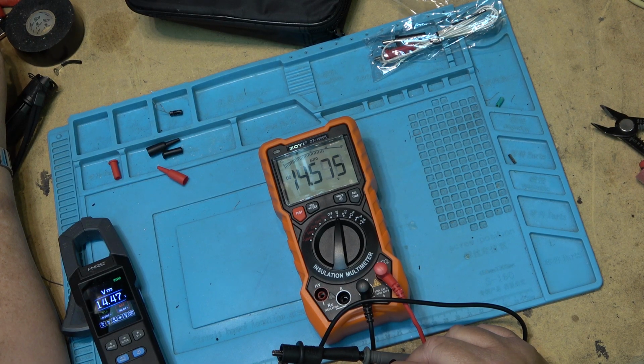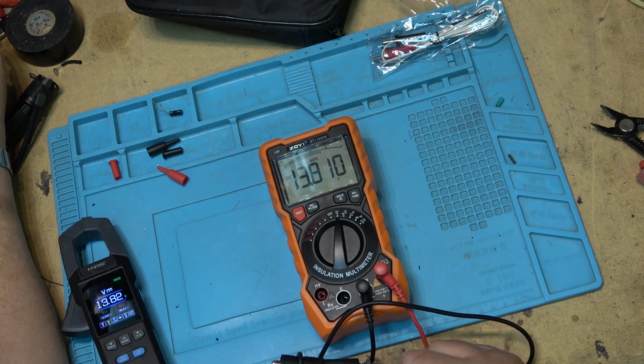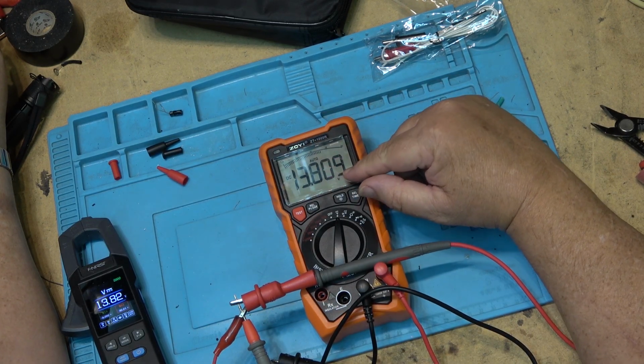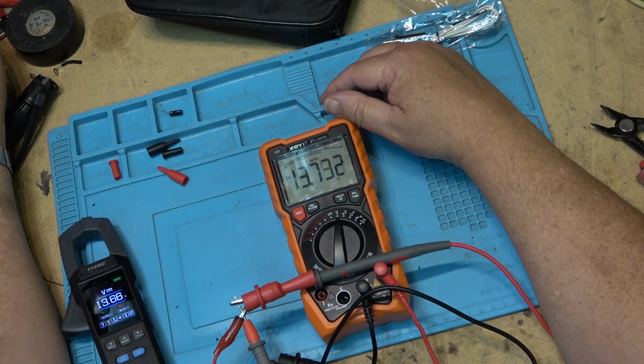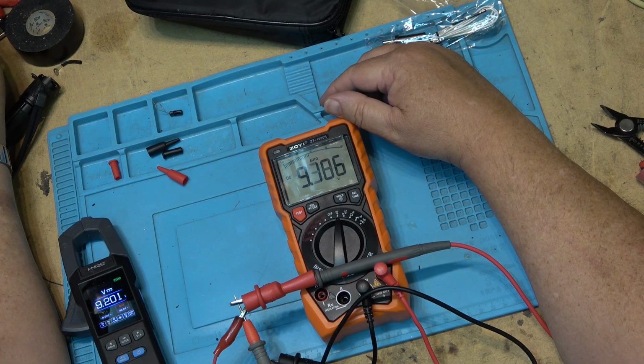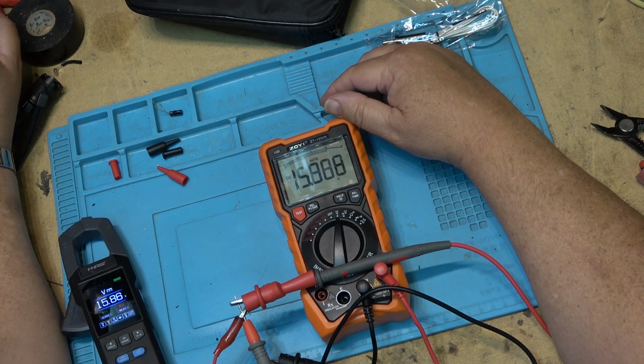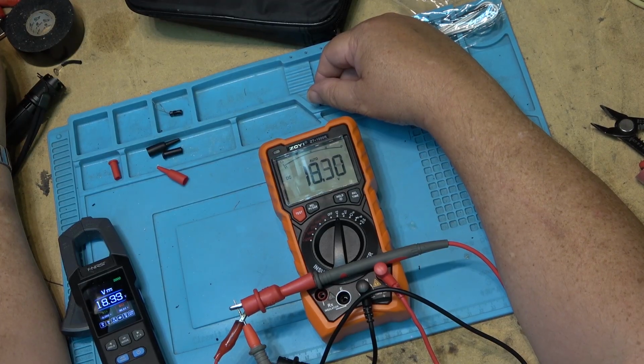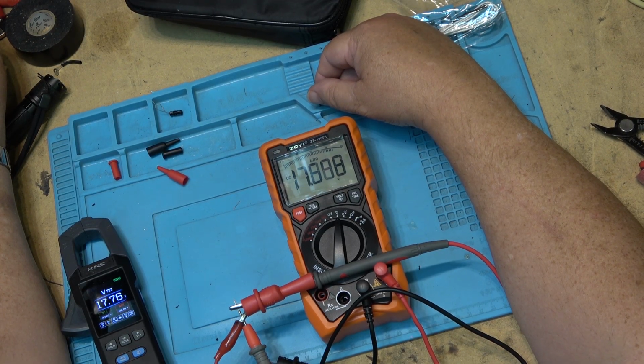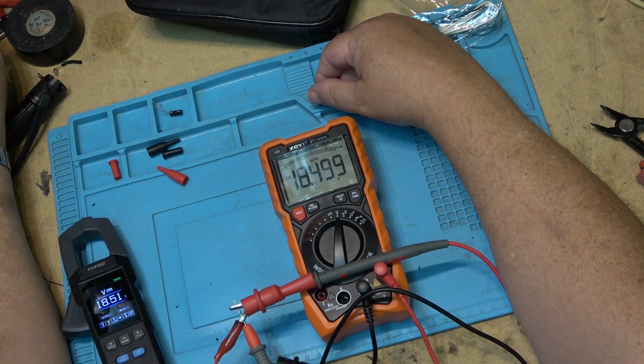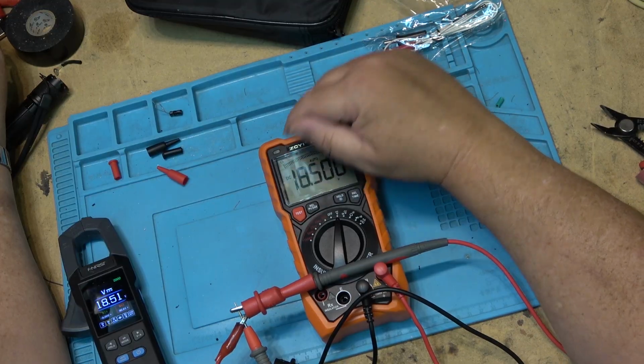Take it down to about 13.8. Got an extra digit of accuracy on the lower voltages. 13.809 versus 13.82. So you get that extra digit of accuracy, and it's fairly quick. It's what's called a 4.5 digit meter. You've got 4 digits, but if the first digit is less than 2, then you've basically got 5 digits, because that digit can only produce the number 1. When you get to 20, it's going to drop the decimal point back.